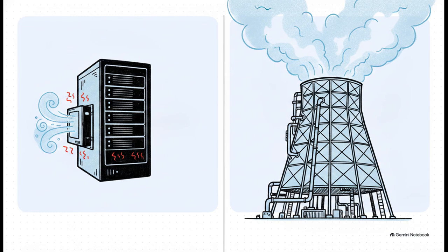Depending on the physical facility you're dealing with, there's a lot of flexibility at this macro scale. On one hand, you can use liquid-to-air sidecars that give you up to 200 kilowatts of cooling without even needing facility water connections. But on the other end of the spectrum, for true megasites, they utilize massive closed-loop water cooling towers. These scale from 1 megawatt all the way up to 50 megawatts or more, maximizing energy efficiency while dissipating unbelievable amounts of heat into the atmosphere.